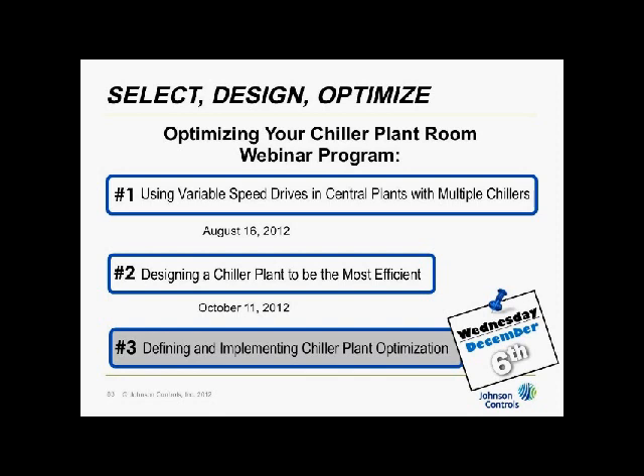how much you can slow the fan down on the tower. Because when you lower airflow in a tower, the approach increases. And that's the reason why we use airflow to maintain minimum condenser water temperature. When you reduce water flow, the approach improves or gets smaller until you reach the point where there's dry spots in the fill, which is why we limit it to about 80% flow. Unless you've got weir dams, or if you've got double spray header, then you really want to stick to around that 80% point and honor what the tower manufacturers don't want you to do, so to speak.